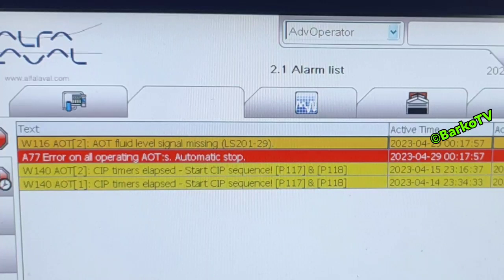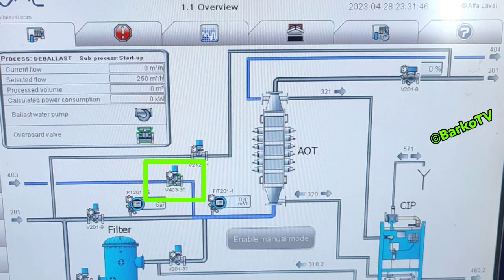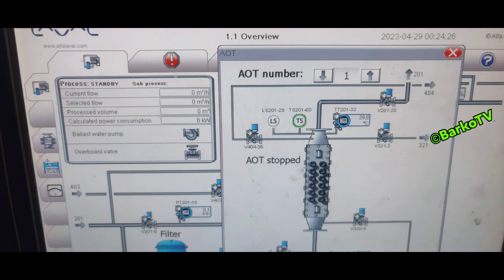The first thing I suspect — that the valve is not opening — is 403-35, which is common to AOT 1 and AOT 2. It's because the same error appears for AOT 1 and AOT 2: fluid level is missing. We will check the mimic diagram at HMI. This is LS 201 attached to the top of the AOT.